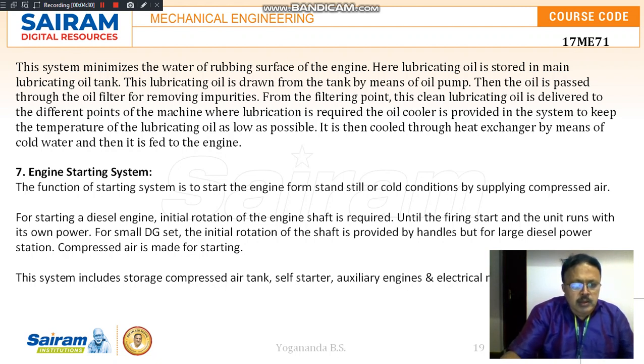The diesel engine will not get started just by switching on the engine. For a small diesel engine set, the initial rotation of the shaft will be provided by handles. But for a large diesel power station, manual rotation of the shaft is not possible, so compressed air will be used for starting the engine. The engine starting system will consist of the compressed air storage tank, self-starter, auxiliary engines, and electrical motor.